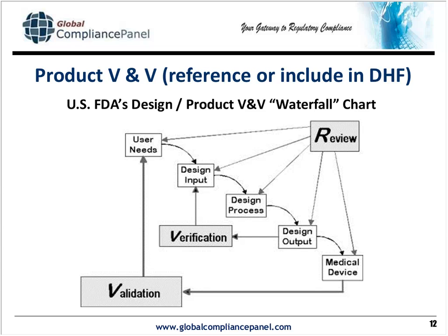But again, you have to determine in your company how you archive documentation. If you, after a set period of time, ship off some of this documentation to some mountain and have it locked in a vault, then you may not be able to access it readily when questions come up, CAPA, root cause analysis requirements require it, or when the FDA audits it. So if that's the case, you may want to include a copy of it in your design history file, even though that may expand its size exponentially. Same with validation documentation, different from what we're talking about here, validation of the process, for example, to build the product or test it.